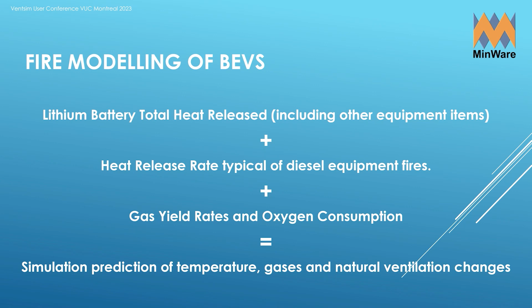But basically, we can actually define a BEV battery in the software independently, and that battery can be defined by the amount of gas that it's released per kilowatt hour. Once you have defined that, you can then put that battery into a machine that you're defining for a heat source or a fire source. You can put in the amount of battery capacity, let's say 350 kilowatt hours, and that battery then becomes part of that machine fire. And if you choose, you can add tyres and hydraulic oil to that fire as well, so that the simulator takes all those into account and generates all those gases, the HF, the CO, the tyres, etc. So it's been made as seamless as possible, and this sort of approach will help people gain some confidence, I suppose, in how to manage the fire risk and the ventilation design challenges for battery fires.